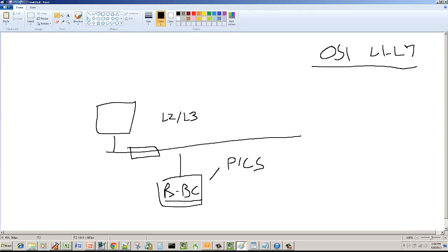All we have to do is log into this BACnet IP server and discover this IP address and discover the device instance, which is a unique BACnet object. We need to make sure that it's unique. We don't want to have conflicting device instances. And then we discover all the objects under it. So I would be able to discover my BACnet IP, and I'd be able to discover all my MSTP field devices. And they would all seamlessly pull in here, and everyone would be happy.